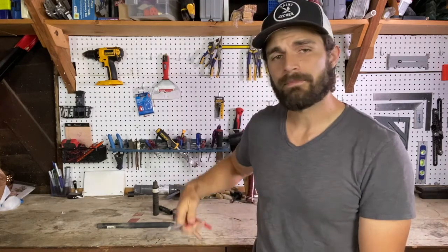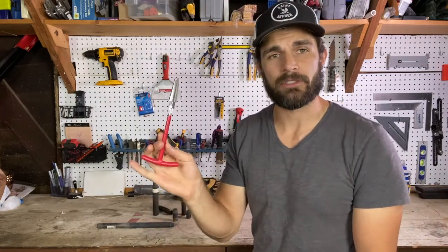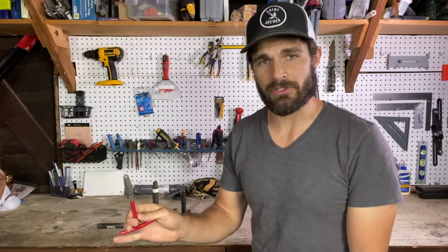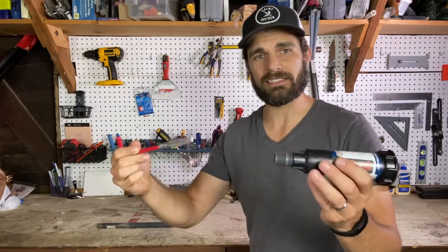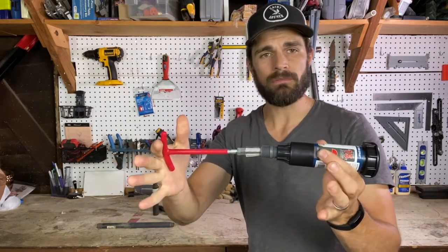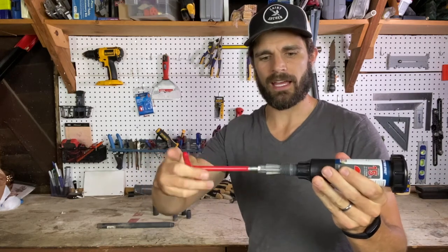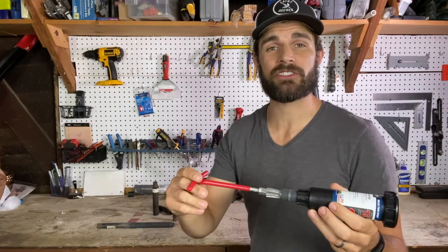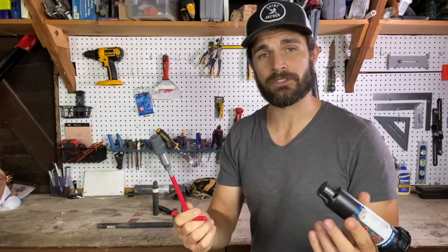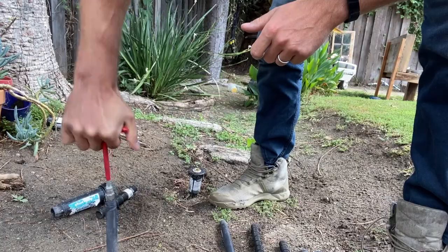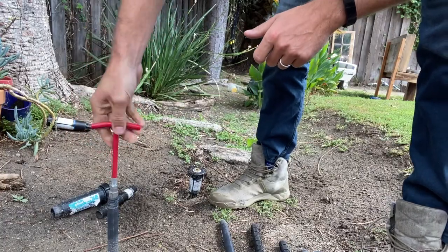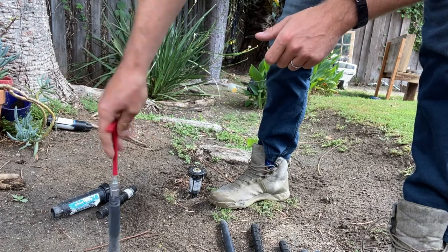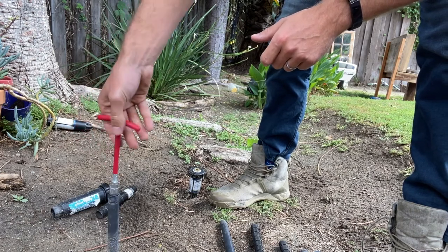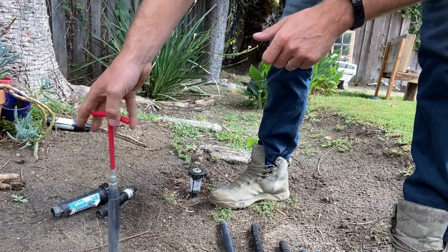Now, if this gets caught inside of your sprinkler head and you need to get it out, there is a tool called a nipple extractor. They're sold at Home Depot. Best $5 you can possibly spend if you're going to do any type of work on your sprinkler system. All this does is it goes into that nipple there, and you can unscrew it, and you can just extract that from the sprinkler head if it's caught in your sprinkler head. If it's caught in your sprinkler system and it is causing a leak, then you just do the same thing. You take the nipple extractor and you put it inside of that nipple and you just pull it out until it releases.